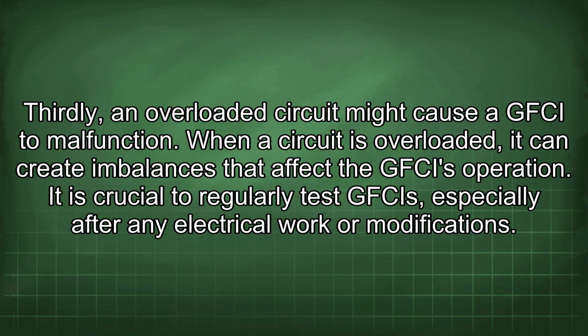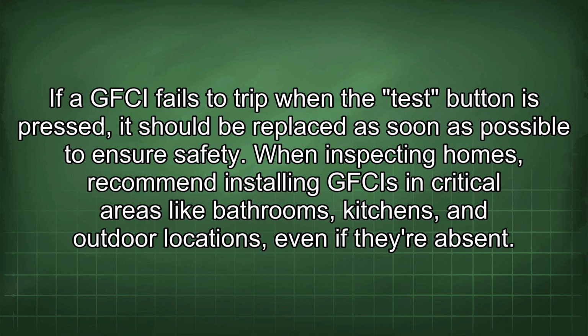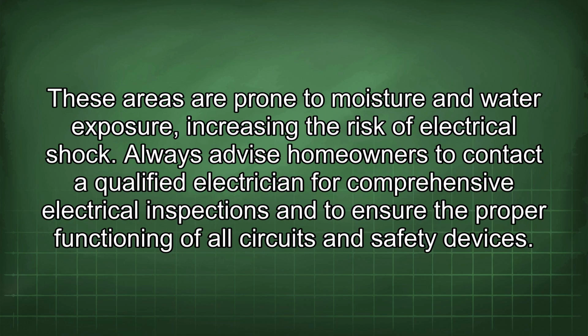It is crucial to regularly test GFCIs, especially after any electrical work or modifications. If a GFCI fails to trip when the test button is pressed, it should be replaced as soon as possible to ensure safety. When inspecting homes, recommend installing GFCIs in critical areas like bathrooms, kitchens, and outdoor locations, even if they are absent. These areas are prone to moisture and water exposure, increasing the risk of electrical shock. Always advise homeowners to contact a qualified electrician for comprehensive electrical inspections and to ensure the proper functioning of all circuits and safety devices.